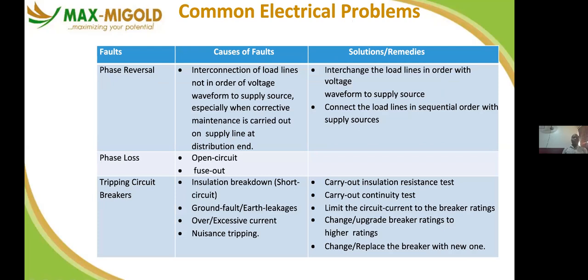So phase reversal occurs when you have a mains failure and they come to rectify it and attempt to connect back the voltage, the cables, I mean, they put red to yellow, yellow to blue, and so on, they mix it up. And when you are operating your three-phase machine, instead of going clockwise, it will be going anti-clockwise. So most especially, it's a problem from the disco, people that come to work on your feeders or so. What do you do? You contact them so that they can come back to rectify it. Phase losses, we have open circuit, could be fuse burnout, and so on.